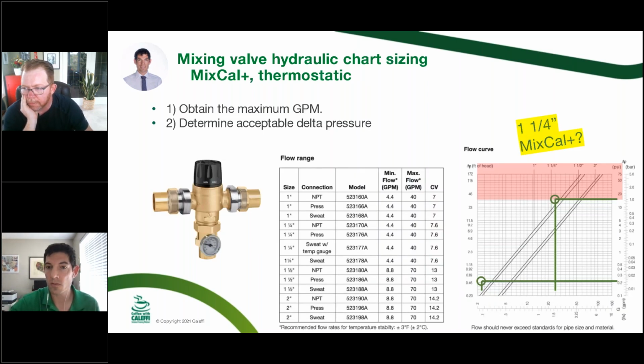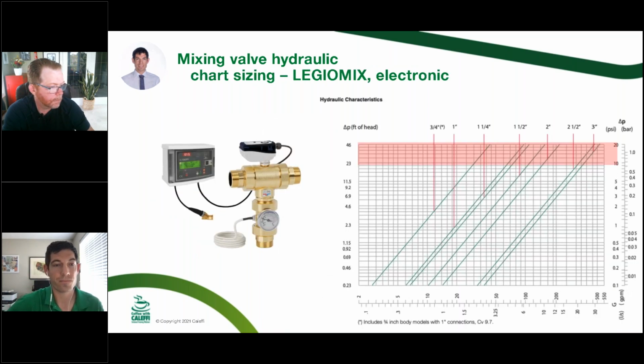So 1.25 inches is where, if you pull up the chart, it lines up, because we want to stay out of that red shaded area at the top, which is where we get past 10 psi of pressure drop. So that 1 inch model isn't going to keep up there. We bumped up to the 1.25 inches, and that's closer because we've got the ability to do that 2 to 30 range. So 1.25 inches there. So let's try it on the next slide with the LEGIOMIX.